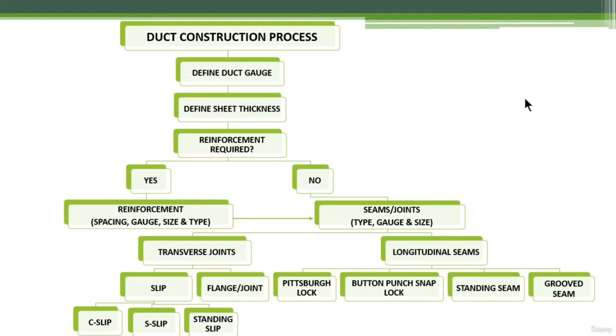Let's go through the construction process step by step. First, you define the duct gauge and duct pressure classification. Once you've specified the duct gauge, you can obtain the sheet metal thickness. After that, you determine whether reinforcement is required or not. If reinforcement is not required, you proceed to define and specify the seams and joints connecting the duct pieces.